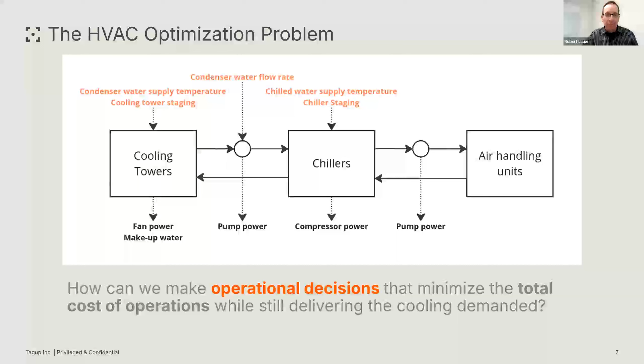For most of the talk, let's just assume the only control I have access to is the set point of the condenser loop temperature. In the middle left of the slide, that's the temperature at which the water circulates, which is controlled by how fast the fans and cooling towers run, but it also has major effects on how efficiently the chiller and any downstream equipment will operate.